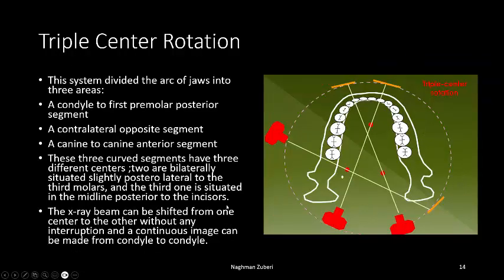Triple center rotation divides the arc of the jaws into three areas: a condyle to first premolar posterior segment, a contralateral opposite segment, and a canine-to-canine anterior segment. These three curved segments have three different centers — two are bilaterally situated slightly posterolateral to the third molars, and the third is situated in the midline posterior to the incisors. The x-ray beam can be shifted from one center to another without interruption, producing a continuous image from one condyle to the other.